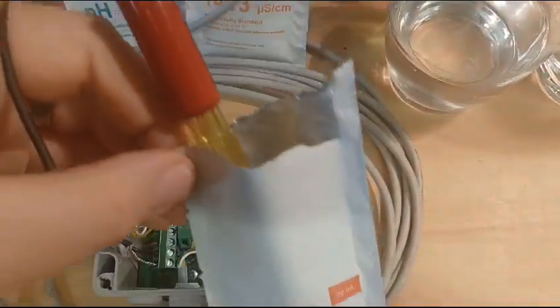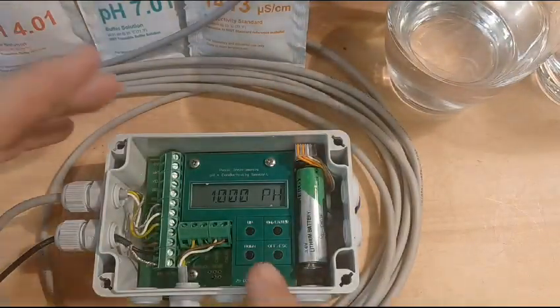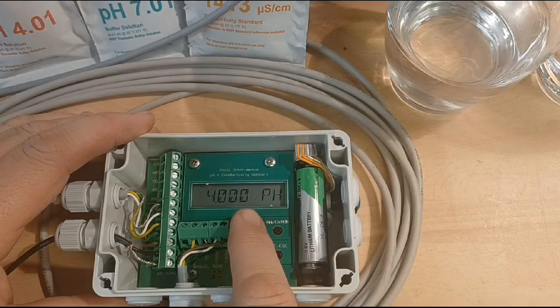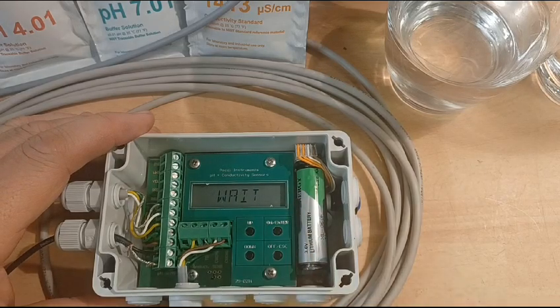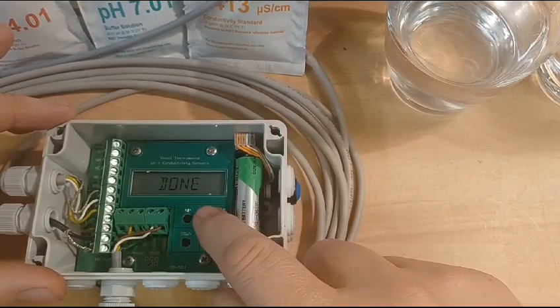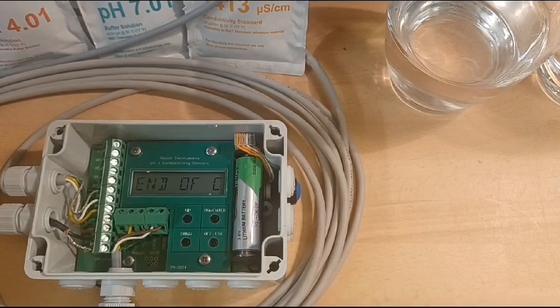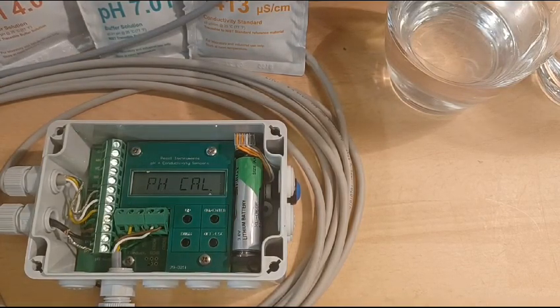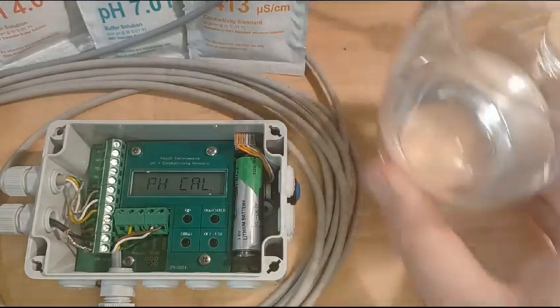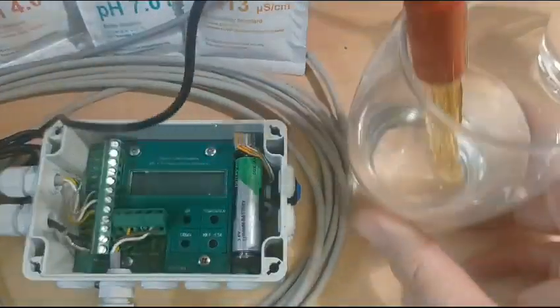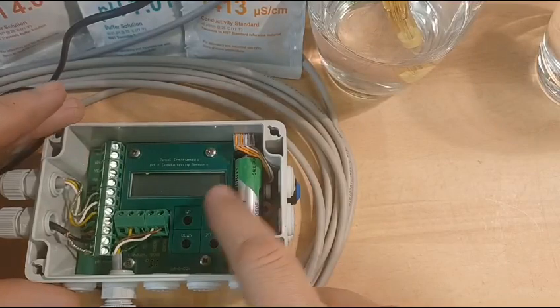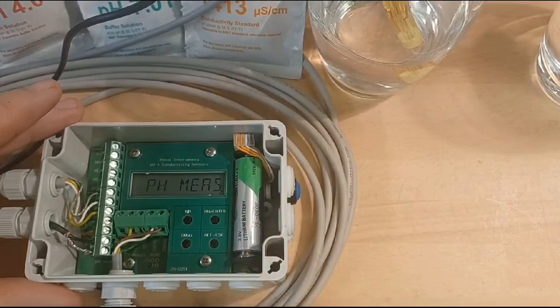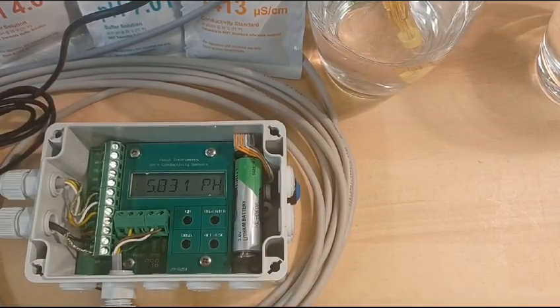So you take it out of 7 and put it into the sachet number 4, like so. And then on the up arrow button, change this to 4 and press OK. And then we wait. After a period of time, you get the done message. Press OK. It says calculating, OK, end of calculation. So you then take the pH sensor out of the buffer solution, and for simulation purposes, I'm putting it into a glass of just plain water. And then you can select on the menu, go to pH measure and OK. It then should give a reading between 7 and 4 in plain water, which in this case is 5.8, which is fine. So that's the pH done.